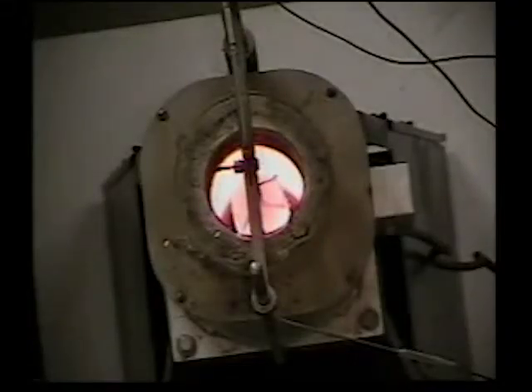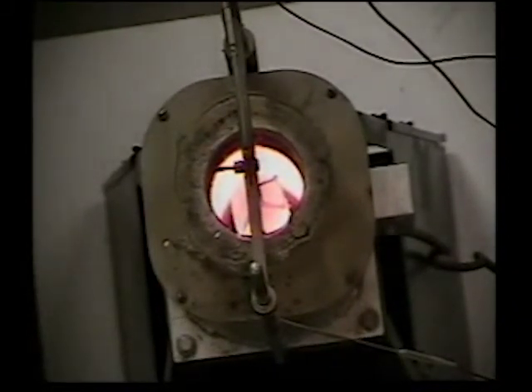Test temperatures in the furnace, on the specimen surface, and in the specimen center are recorded throughout the 30-minute duration of the test. The specimen temperature begins to rise in the hot environment and the first criteria for successful test completion — flaming — can be examined. The specimen shows no evidence of flaming.